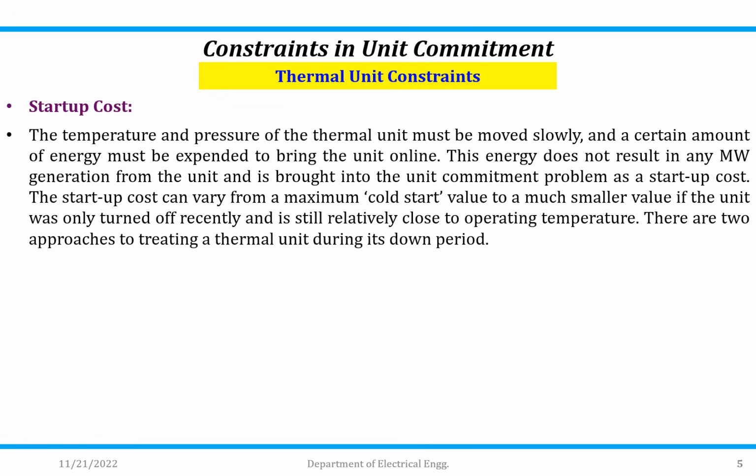When the temperature and the pressure of the thermal unit are increased and a certain amount of energy is expended to bring that unit online, that doesn't mean it will immediately produce some amount of power in megawatts. No, it is brought into the unit commitment problem as a startup cost. The startup cost can vary from a maximum cold start value to a much smaller value if the unit was only turned off recently and is still relatively close to the operating temperature.